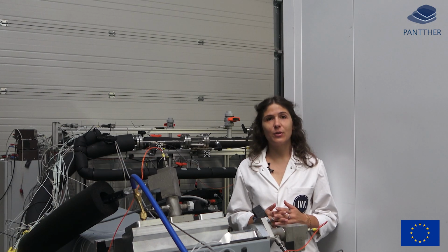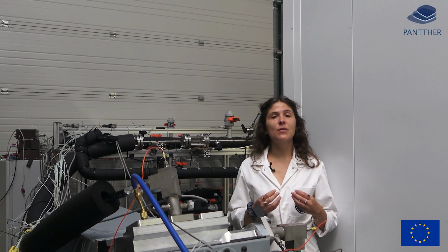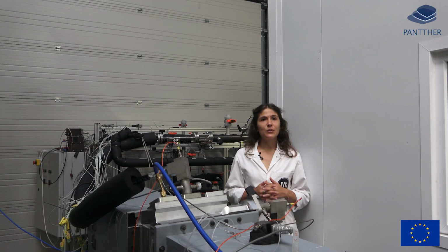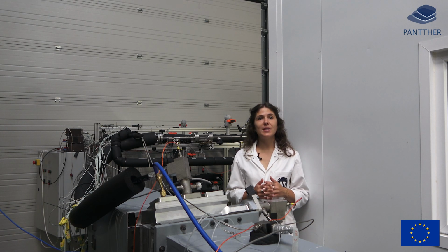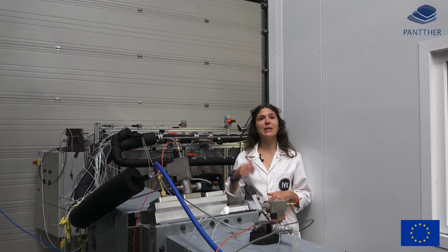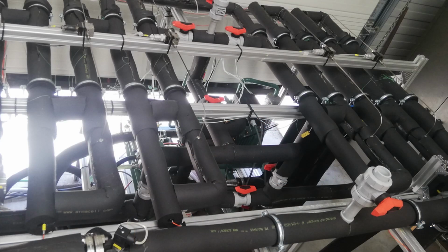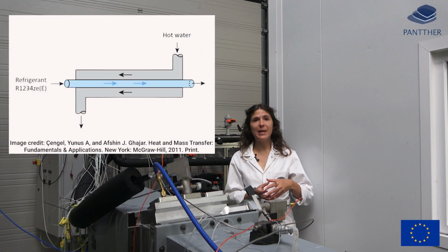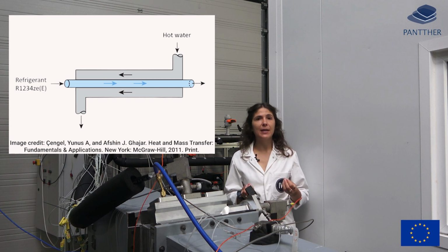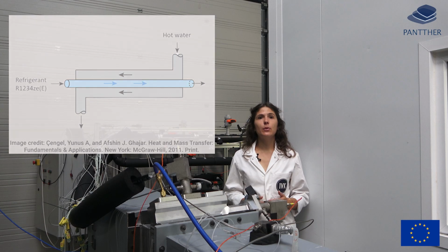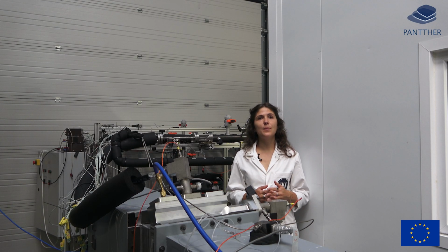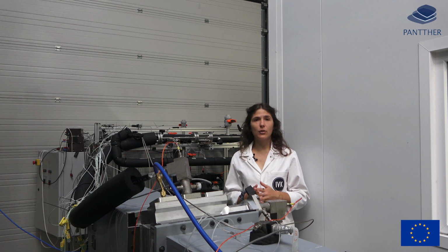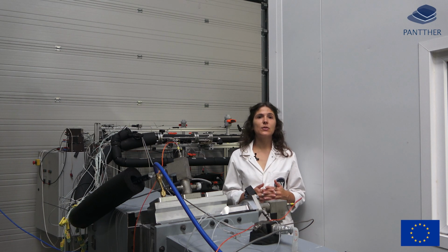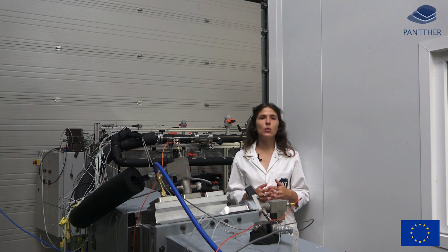So the refrigerant that we used is R1234ze(E) refrigerant, which is a new generation of refrigerant and that has a very low polluting index. So in the first time we tested this refrigerant on a simplified evaporator test section that you can see behind me, which is a double heated pipe. So the water is flowing outside the refrigerant pipe and is heating up and evaporating the refrigerant inside the pipe. So this is a very simple geometry, but it allowed us to obtain heat transfer coefficient and pressure drop correlation that we compared with the literature, because the thing is that this refrigerant, as it is quite new, is still not fully characterized in the literature.